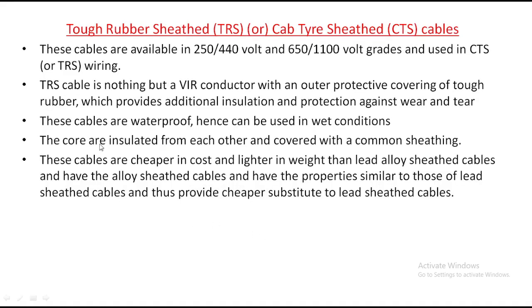The next category of cables is tough rubber sheathed or cab tyre sheathed cables. These cables are available in the same ratings, that is 250/440 volts and 650/1100 volts grades, used in CTS and TRS wiring. See, TRS cable is nothing but a VIR conductor with an outer protecting cover of tough rubber. So it is nothing but the same.